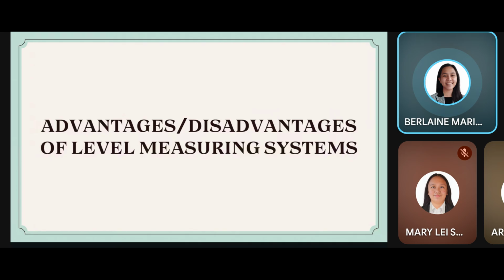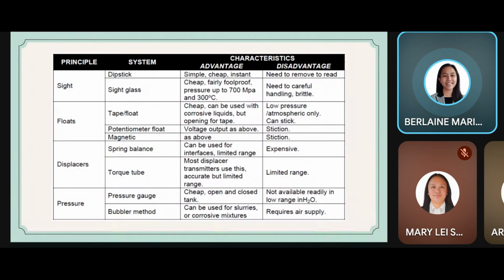Lastly po, for Chapter 7, the advantages and disadvantages of level measuring systems. Next po. Ang una po is yung sa mga sight methods, which is the dipstick and sight glass. Ang dipstick po is simple, cheap, and instant, giving a direct reading right away. Its disadvantage is that it needs to be removed to read, which means it cannot provide continuous measurement. Sa sight glass naman po, it is cheap and fairly foolproof, and it can handle pressure up to 700 megapascal and 300 degrees Celsius. Its disadvantage is it needs careful handling because it is brittle.